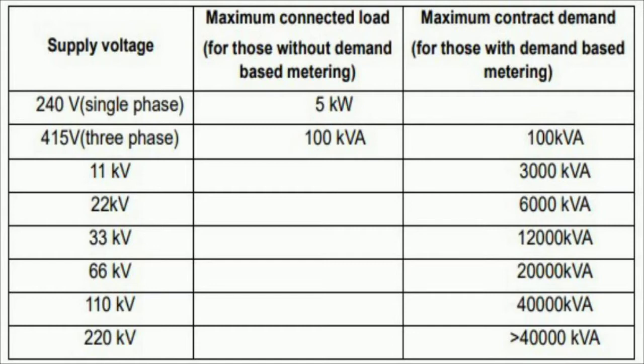This is clause number 8 of the Kerala State Electricity Supply Code 2014. Based on the electricity supply code, it can be seen that for loads up to 5 kW, only single phase 240 volt supply is required. For loads up to 100 kVA, 3 phase 415 volt supply is required. And for those loads above 100 kVA and up to 3000 kVA contract demand, 11 kV supply is required.